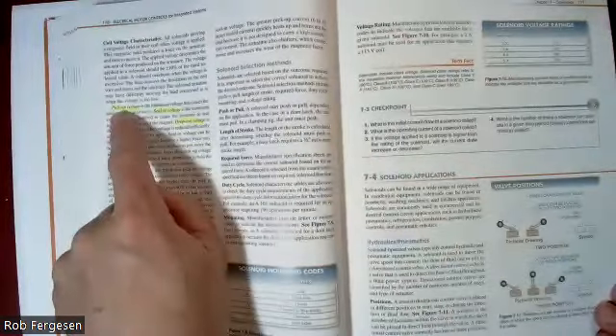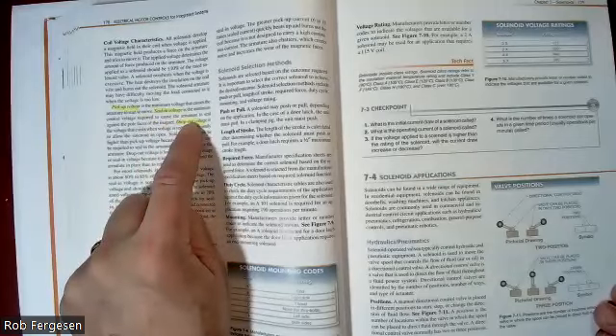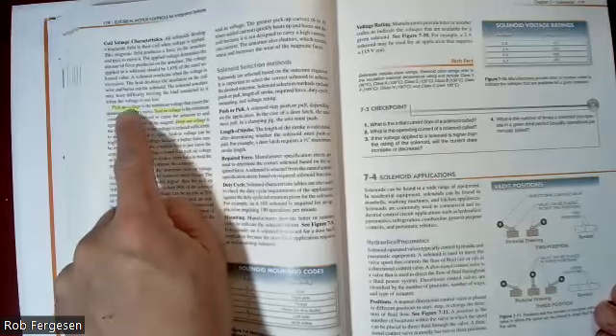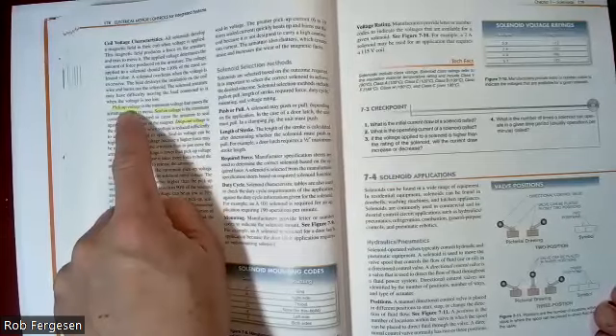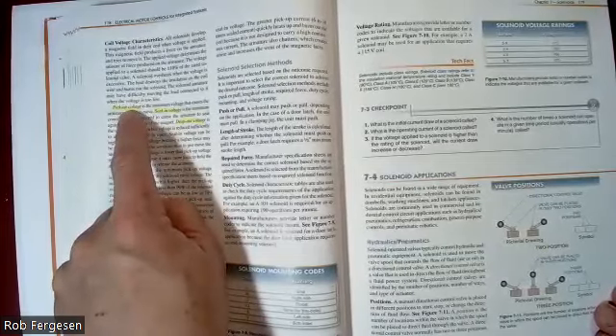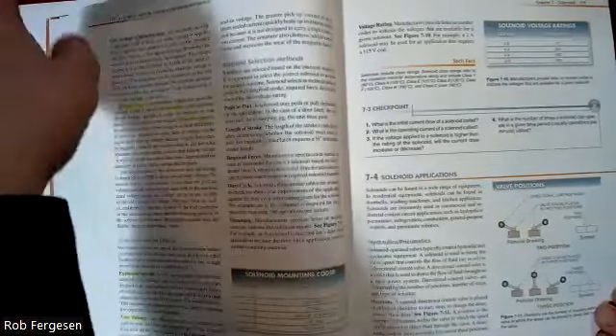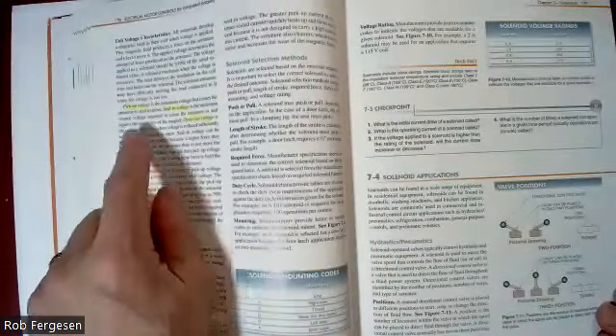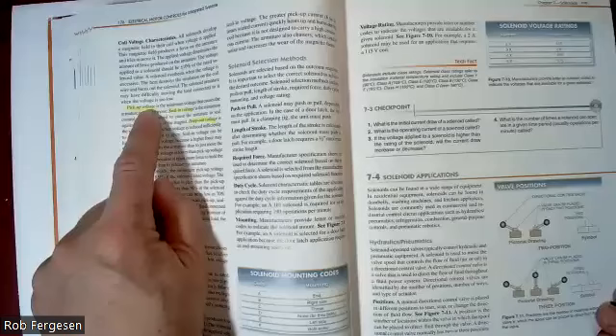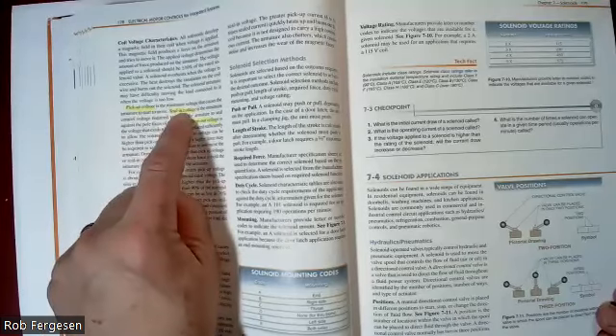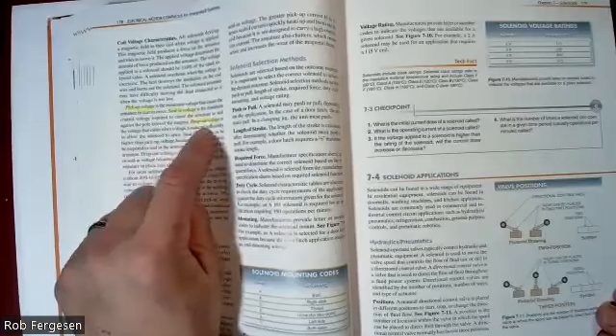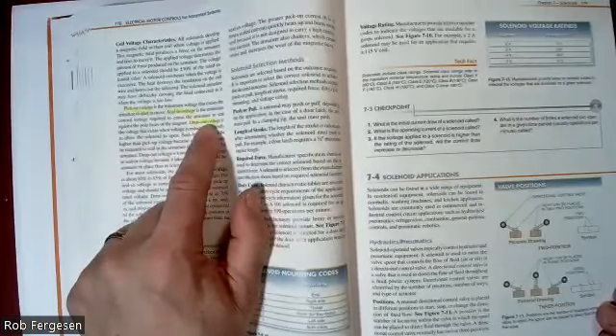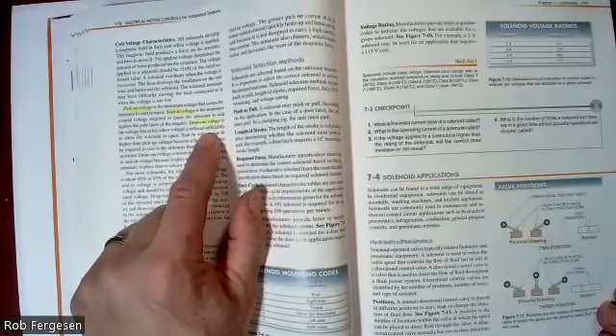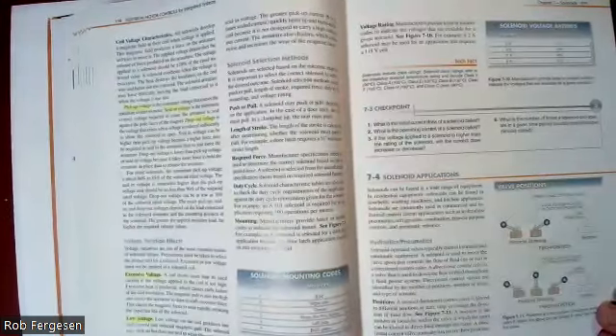Key aspects of a coil, I'm going to highlight 3 terms that are critical: pickup voltage, seal-in voltage, and dropout voltage. Pickup voltage is especially critical in low voltage relays that are associated with devices that might be built onto your PLC. Pickup voltage is just enough voltage to cause that relay to close. Seal-in voltage is just enough voltage to keep it closed. And dropout voltage is the point by which when you reach that lower voltage, it pops open. That's your dropout voltage. So those are very important terms.